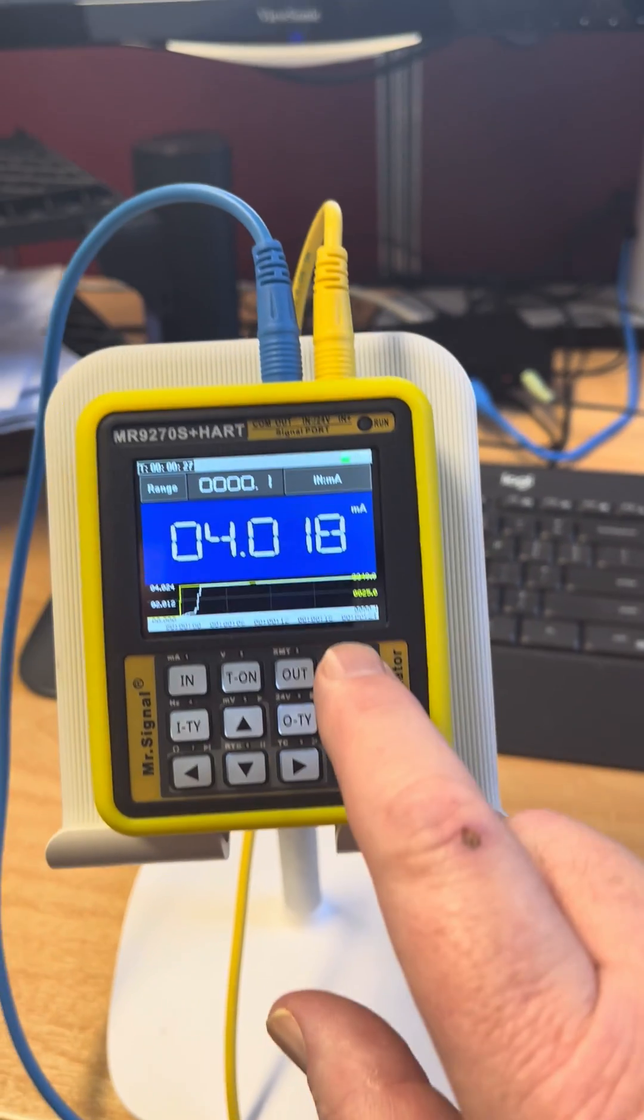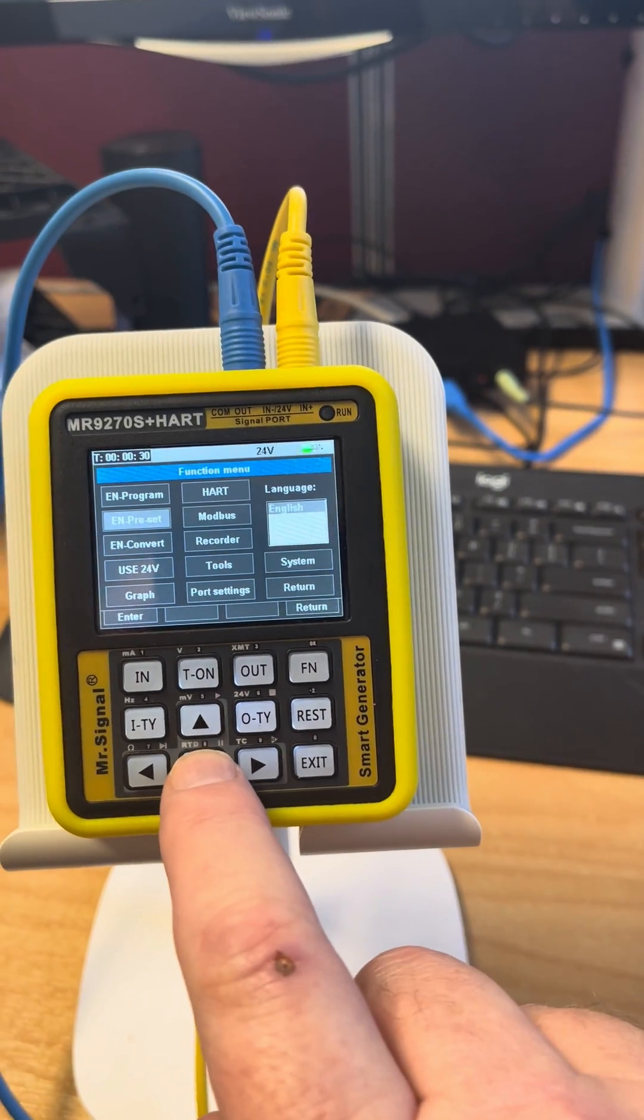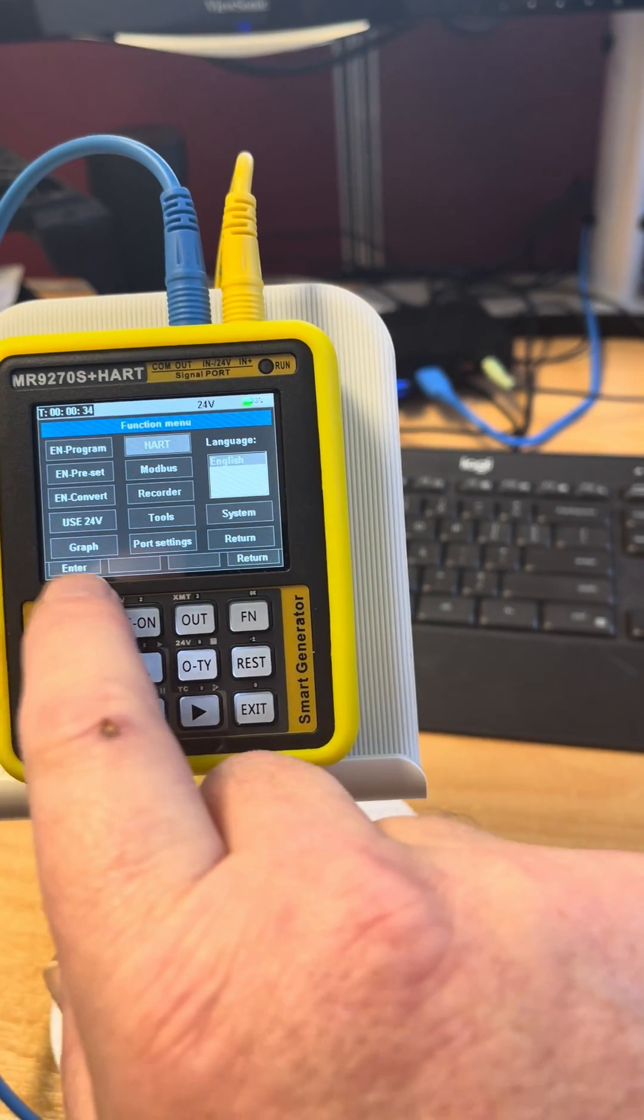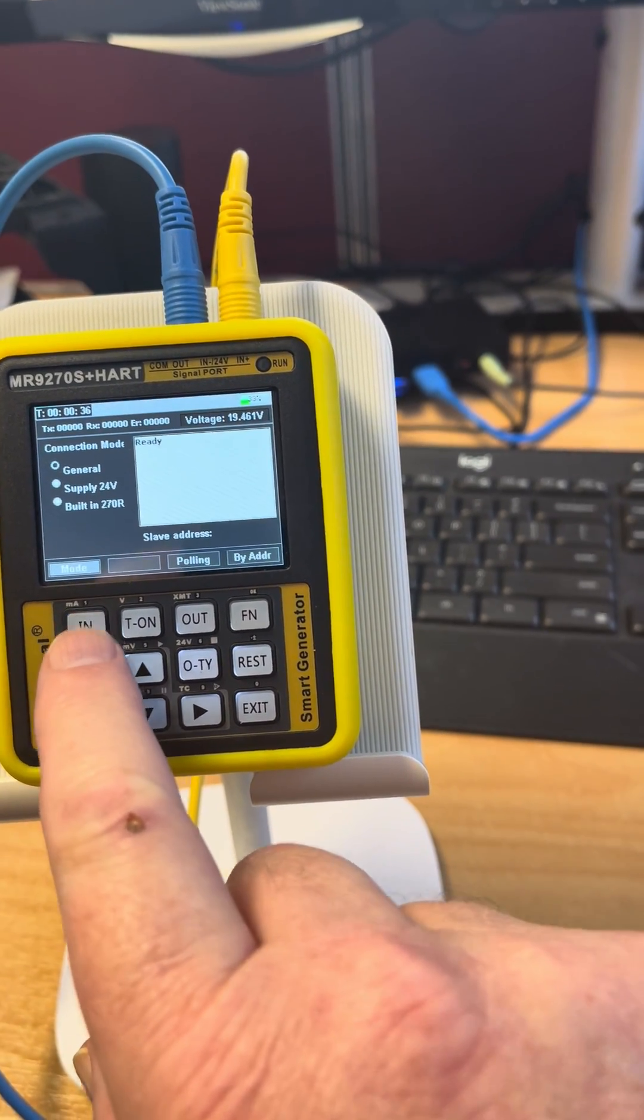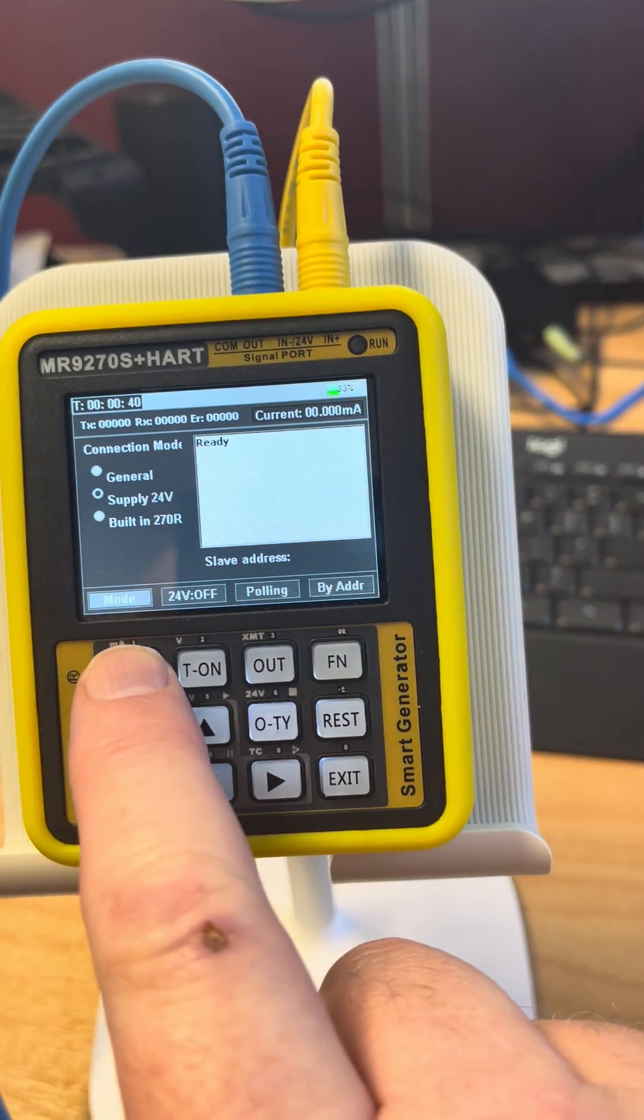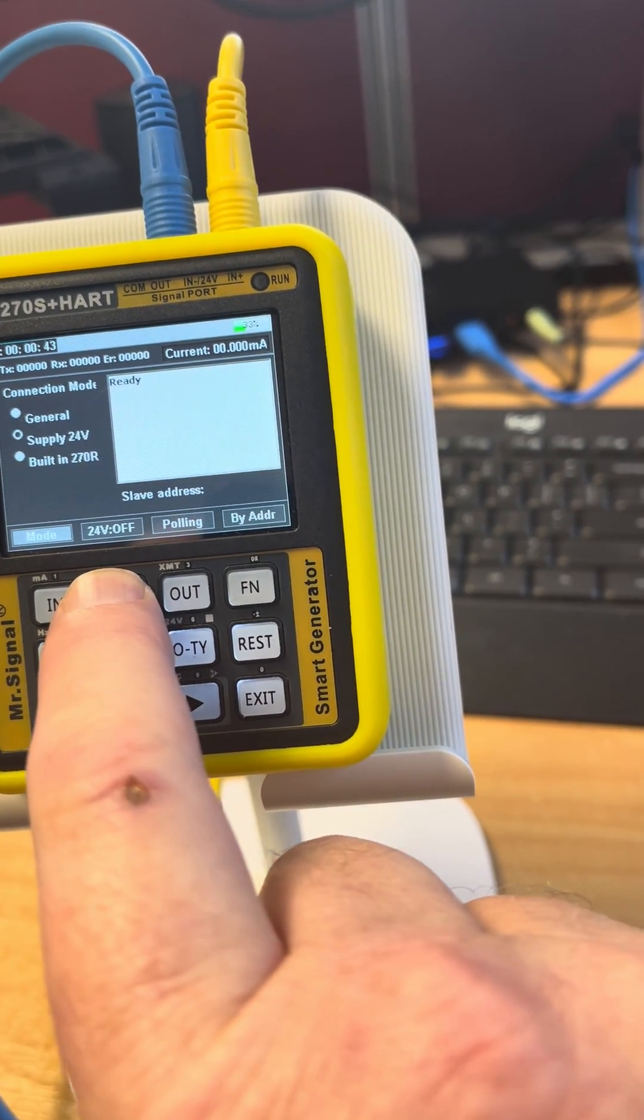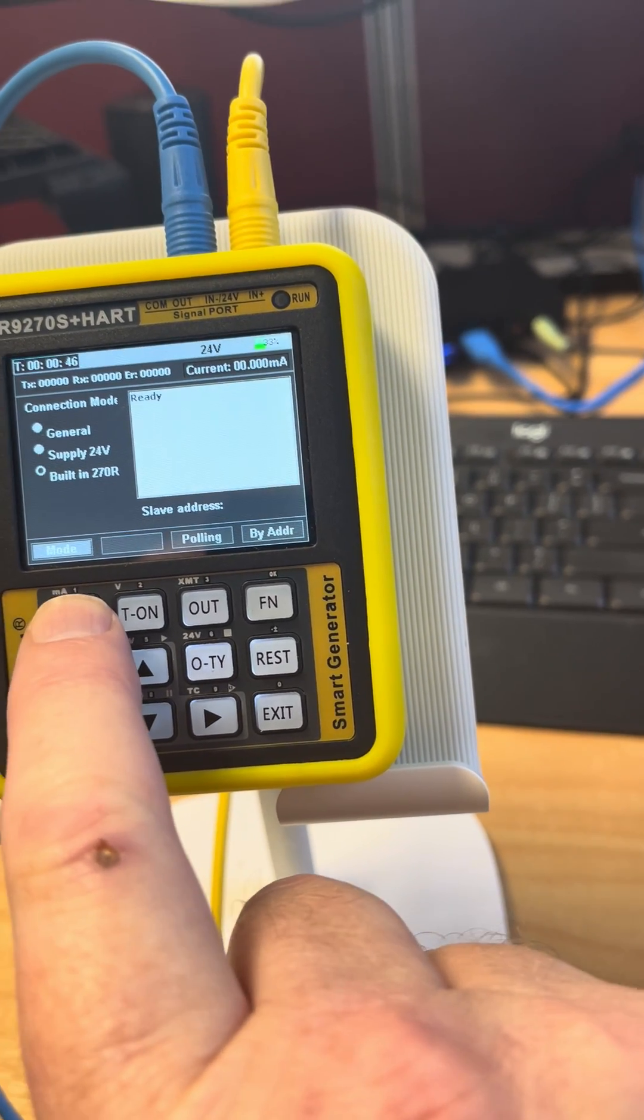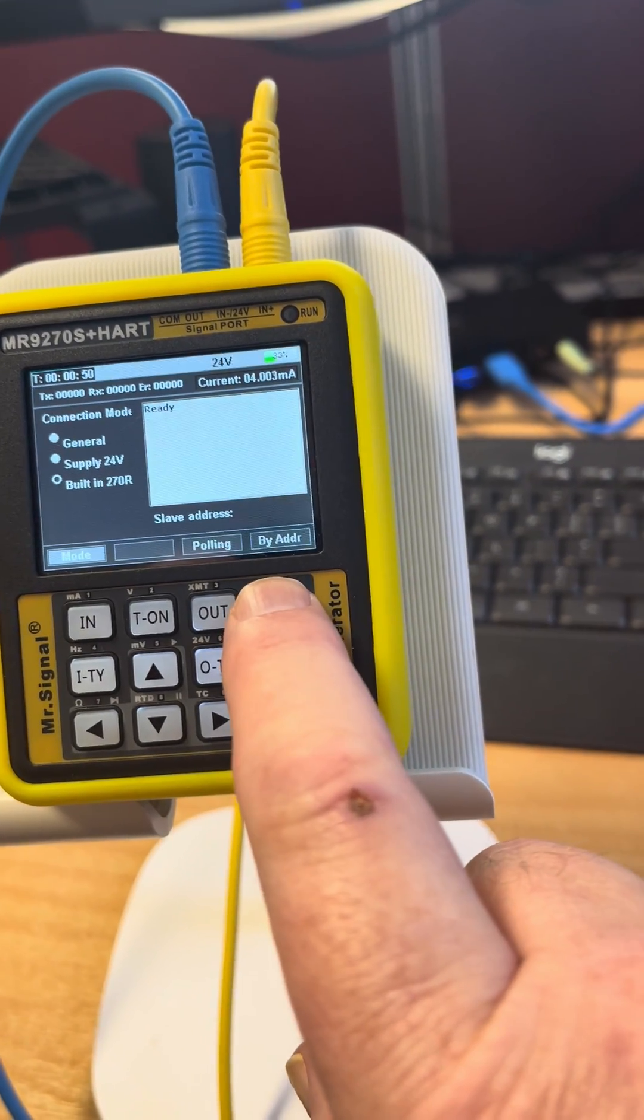If we now move to function and go to HART, first thing we have to do is go down to supply 24 volt and turn that on, then move down to the 270 ohm and hit by address.